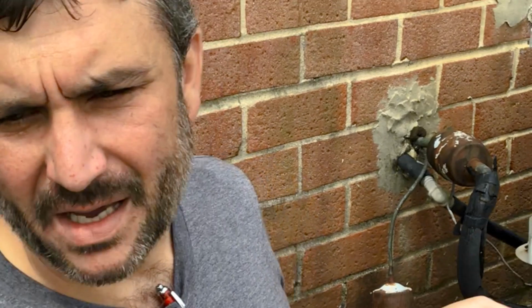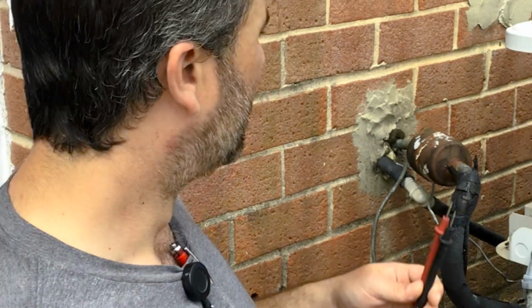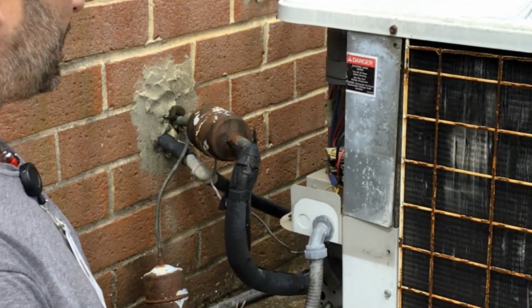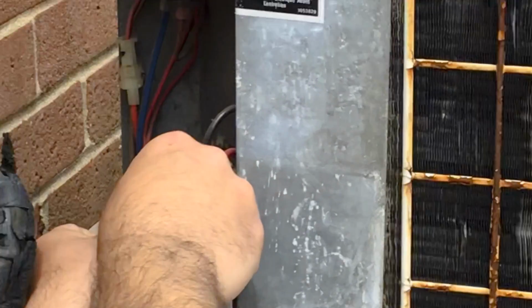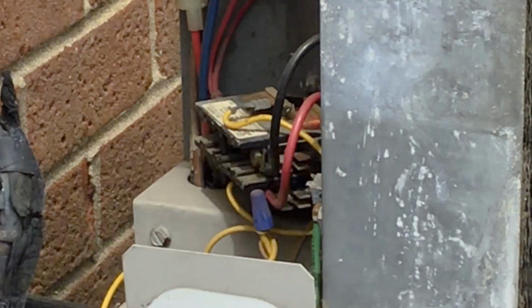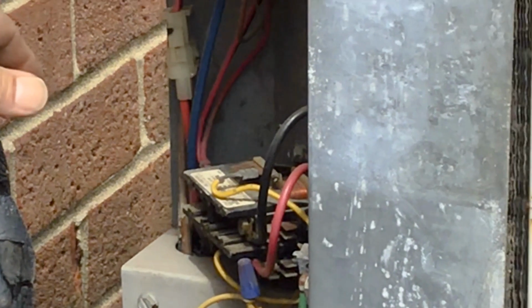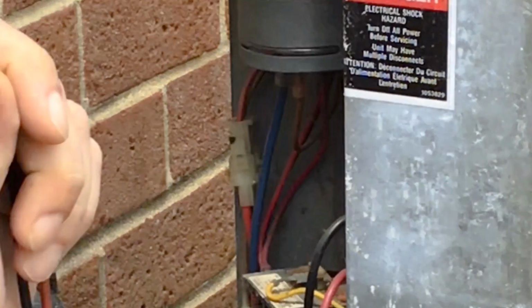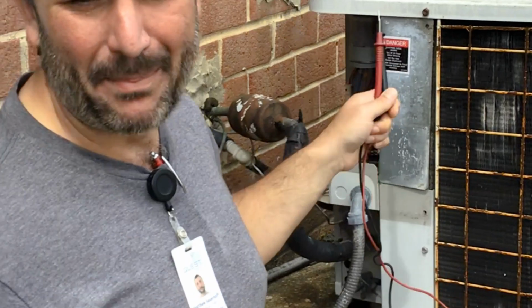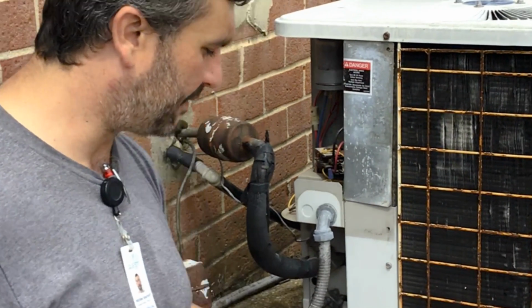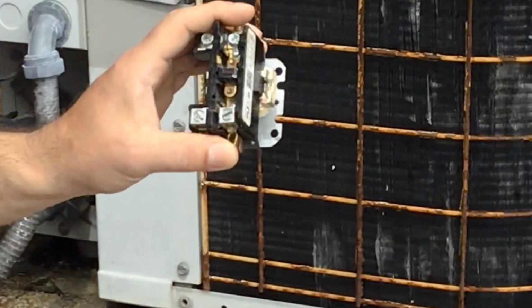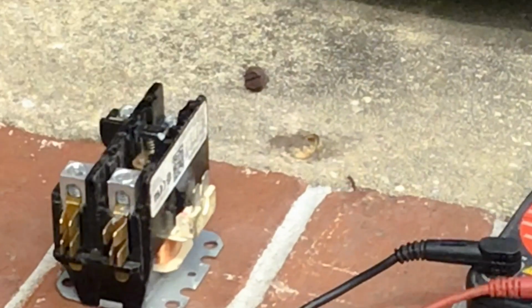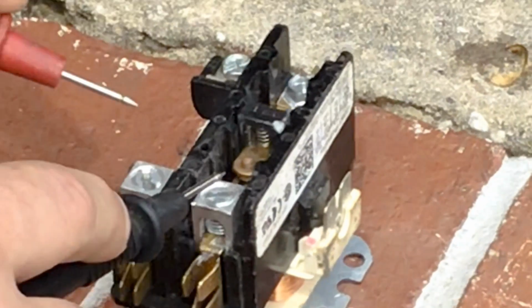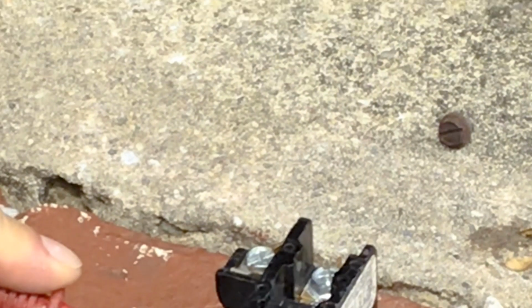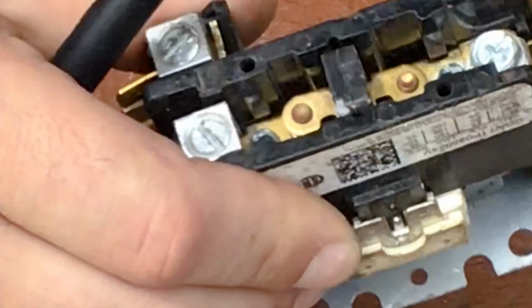Okay, so we talked about changing the capacitor. So you changed your capacitor already, and you have your 240 volts going across your contactor, and your wire connections, your spade connectors, are all intact, and your fan still isn't running. You've got a bad fan motor. You're going to have to change it out. But real quick, I'll show you a contactor here that's out of the unit. You want to test your line side, which is your power coming in, for 240, and then make sure you've got 240 on the other side, because sometimes even though this is pulled in, this device can be bad itself.